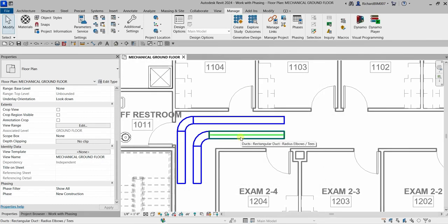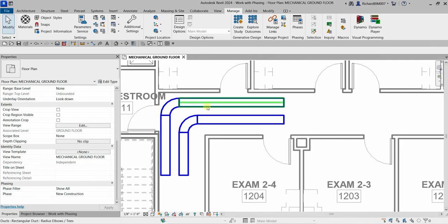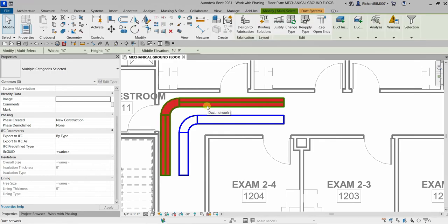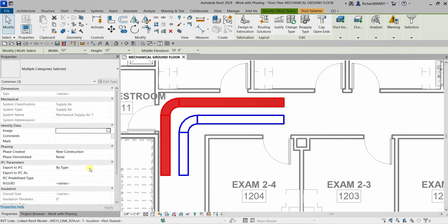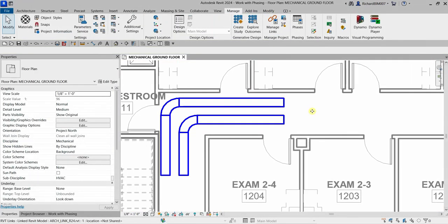Now I'll select the topmost duct run — hover the pointer, press Tab once to select the entire duct network including fittings, then click to select. I'm going to change the phase: Phase Created set to New Construction, Phase Demolished set to None. This creates a new element in the New Construction phase.